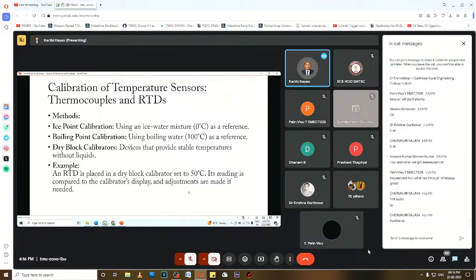In boiling point calibration, you apply the sensor in boiling water to check the temperature. Thermocouples and RTDs, the temperature sensors, have to show the correct reference value, whether it's 0 degrees Celsius or boiling point, to be considered perfect.